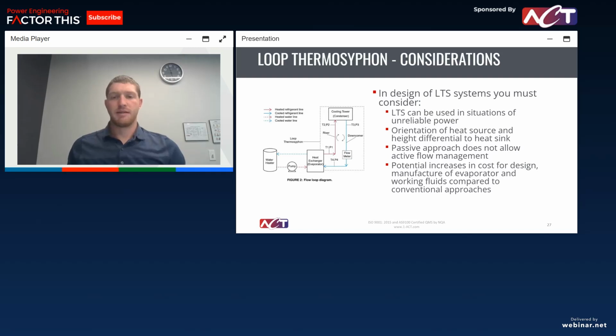In a loop thermosyphon, that's not possible, but when you look at the design, you're designing around how much fluid flow you want, and it's kind of set. What you can control, and what we'll often control, is we'll have temperature and pressure sensors, and that will control our fan speed. So we can still set evaporator temperature, set temperatures that we want to see at our junctions through our electrical components, and control the system that way. But you don't have that active flow management of the fluid itself.